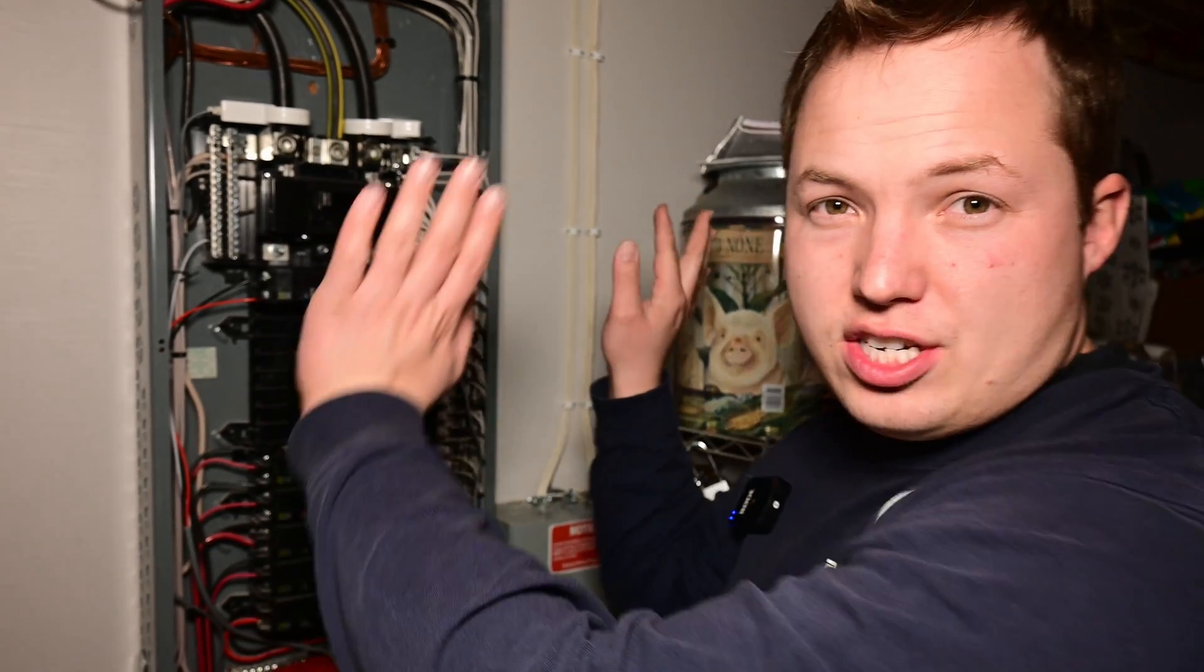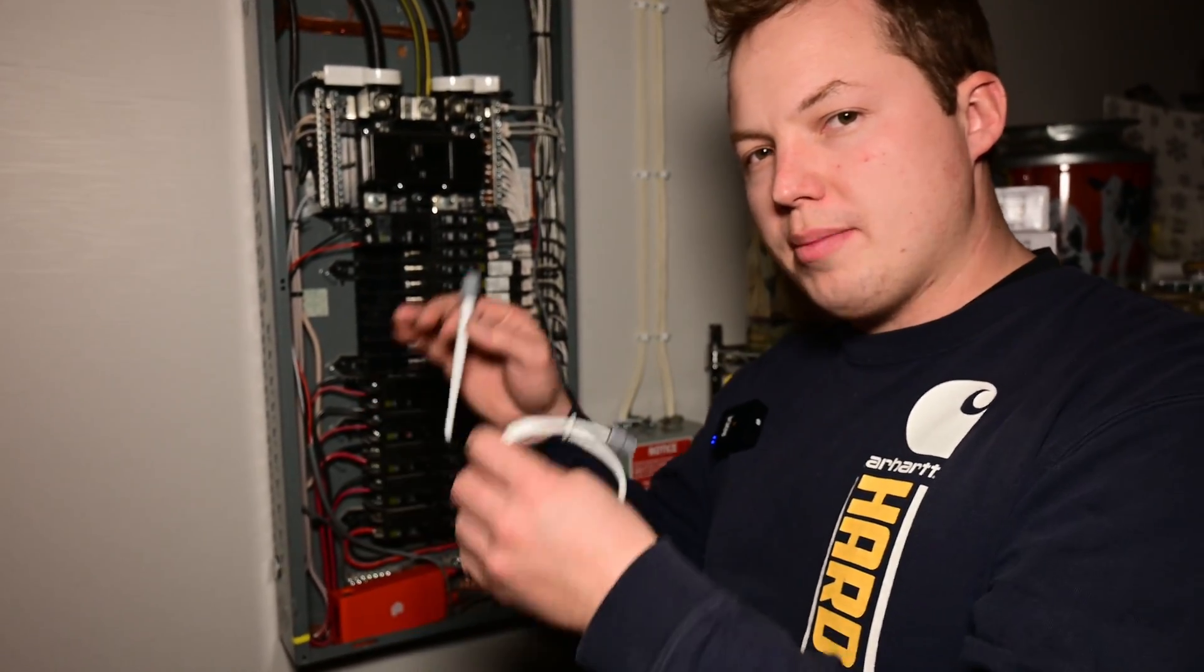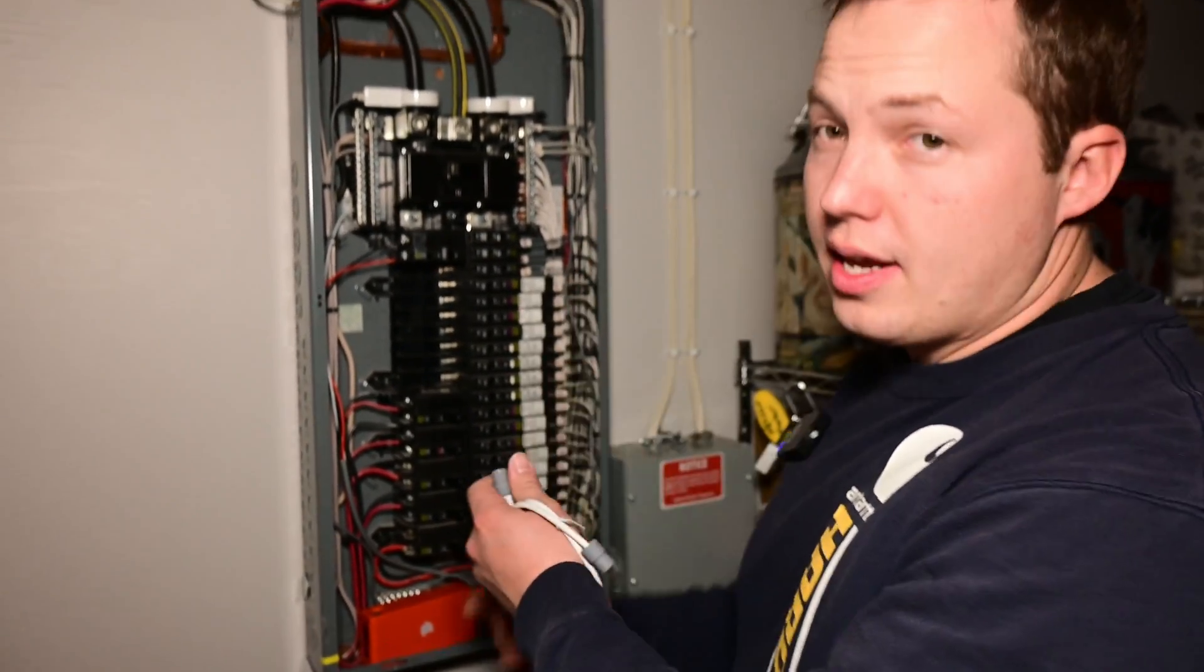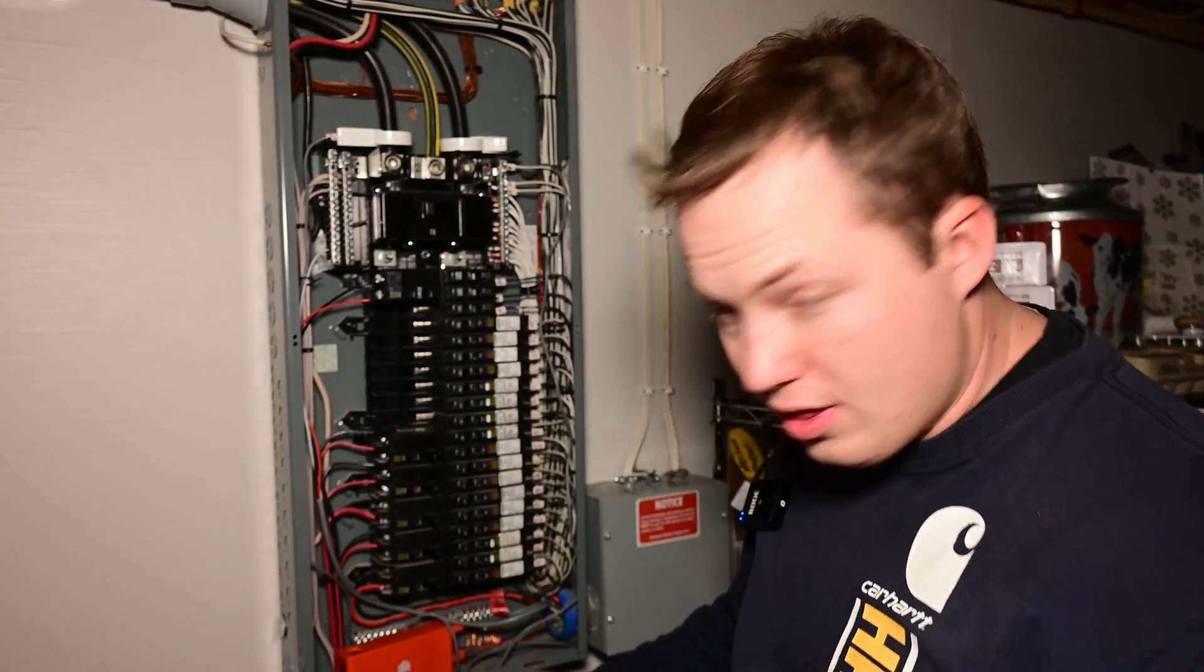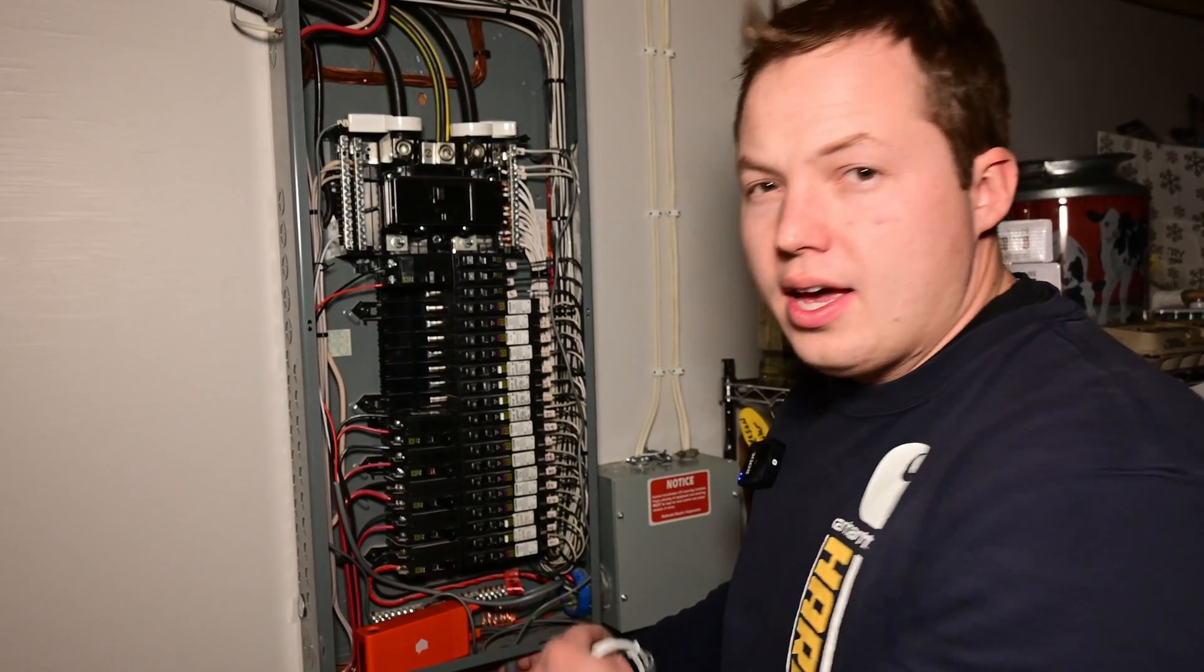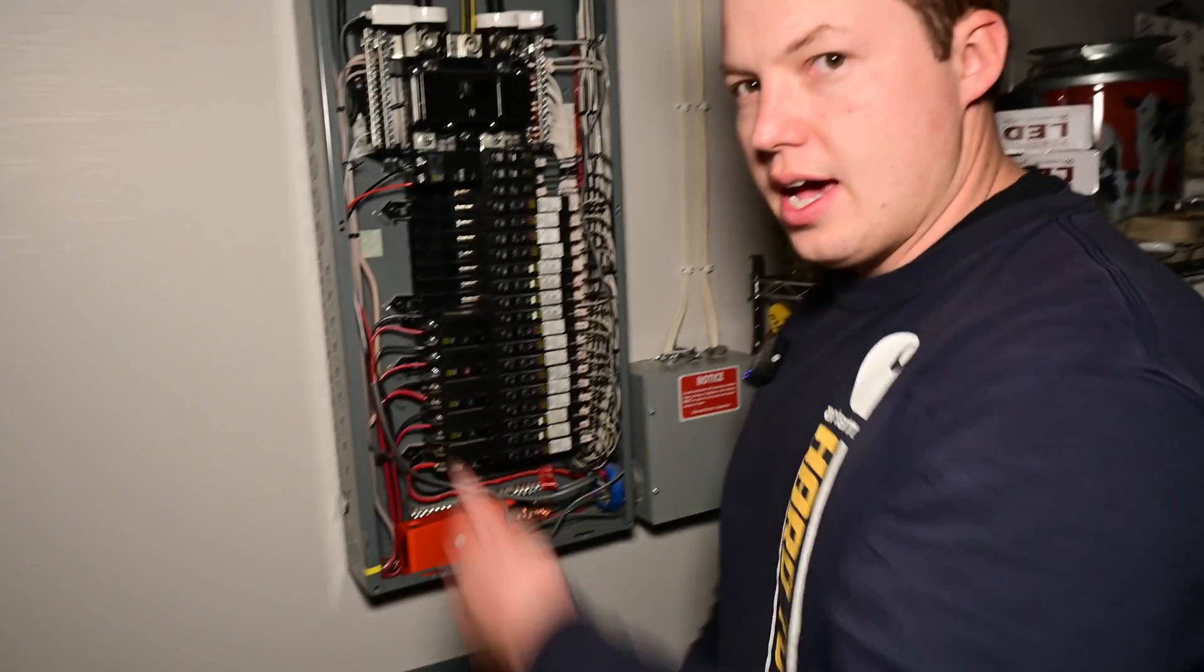If your panel happens to be flush-mounted, meaning that the panel is recessed back into the wall, you will take your antenna and you'll have to stub it down. So you'll open a knockout in the bottom of the panel, most likely, or the top, depending on your scenario, and then this antenna is going to stick down in the wall. It'll be behind the drywall, and it'll still work perfectly fine. So if you do have a flush-mounted panel, you'll be going down or up with your knockout instead of going out the side.